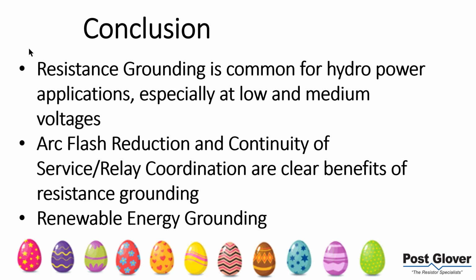There were actually no additional questions. There were some comments about the microphone that I addressed, and somebody did point out earlier on one of your slides, and I assume it was on the resistance grounding slide, that there is no arc flash hazard. And of course, the talking point was there's no arc flash hazard from a line to ground fault. Obviously, if there's a line to line fault, there could be an arcing event. It was probably not the greatest idea to state it that way, although I addressed it clearly in the presentation. The problem is if somebody's reading this later, they may get the wrong impression. But that's clearly for line to ground faults, and actually the way they say it in the IEEE as well, they make it very dogmatic like that. However, the context is for line to ground faults.